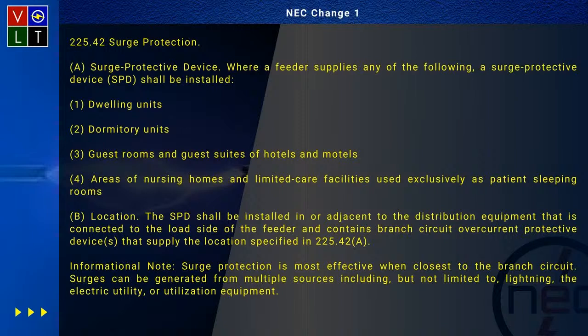Okay, well I'll be honest, I actually like this change. I didn't like it at first because I thought, how is it the code's job to shove this down people's throats? But Corey Hanna made a really good point - he said, dude, we have like $10,000 worth of computers in our house, and you're spending maybe an extra $20-$30 to have an SPD main on your panel. Who cares? Then to rebuttal what Mike was saying, that you'd have to have SPD protection for each unit - that could be accomplished with a Type 2 SPD. Sure could, and that would be compliant for however many units you wanted, so you wouldn't have to have it for each individual breaker in that multifamily dwelling unit. That's right, and that's why you've got different surge protection device types, just for that reason.